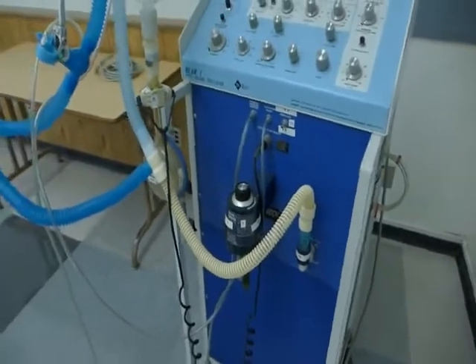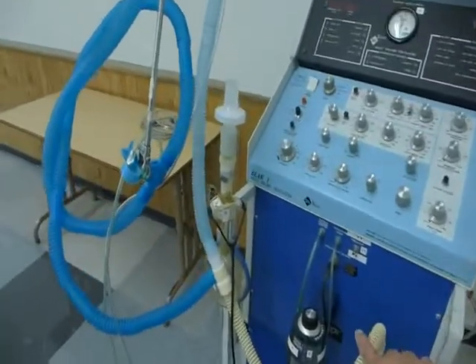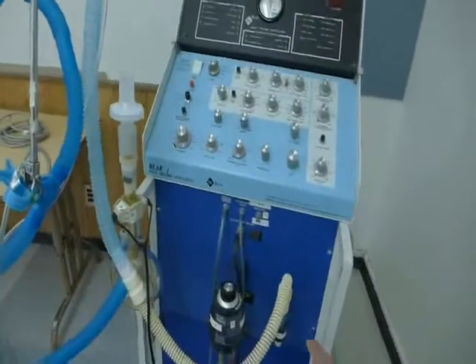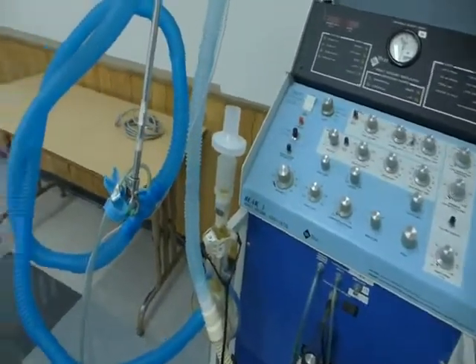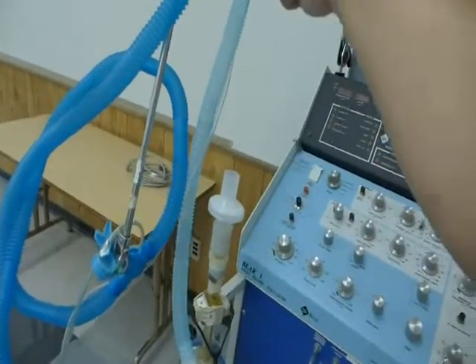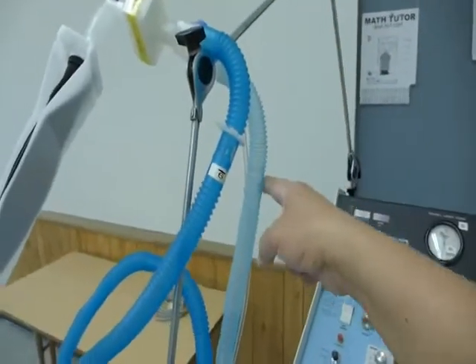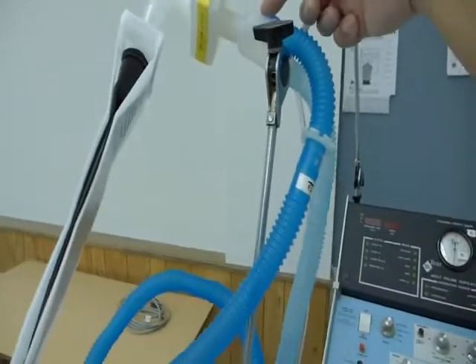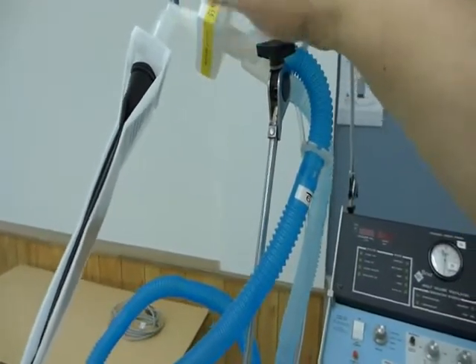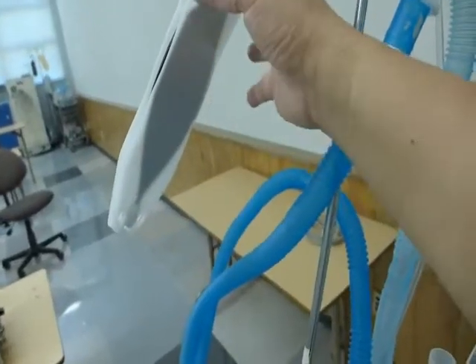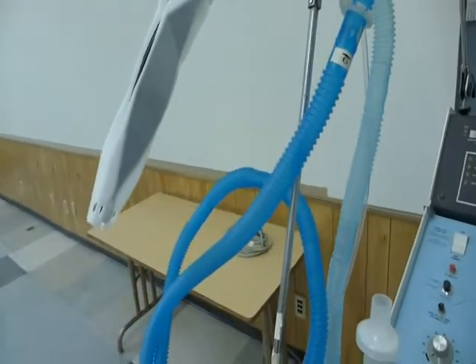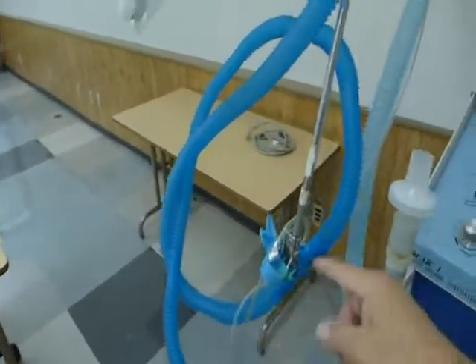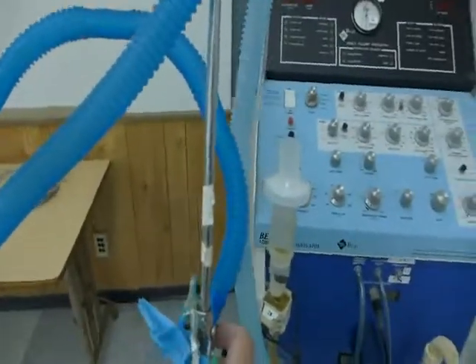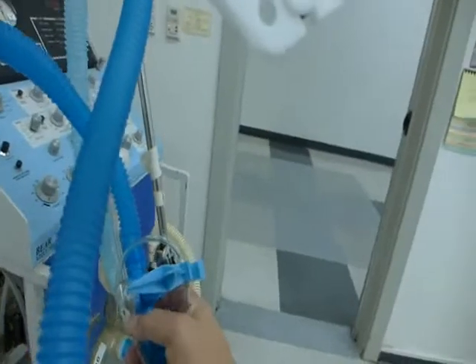Okay, now we're going to talk about the breathing circuit. The breathing circuit has two sides. One is the inspiratory side of the breathing circuit, and it goes to the patient. They have the Y here, and then they have a filter, and then this goes to a test lung. I use this as the patient, a test lung for the patient. And then when the patient exhales, it comes back to here, past this valve we call number 4. You can see that.